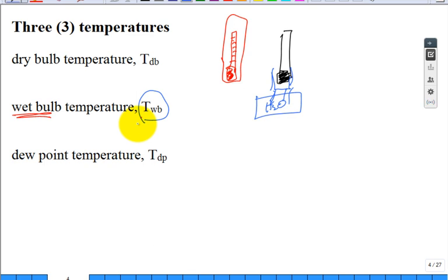So I can now turn it. I can put the two pieces together, push it in or out so far such that the 75 or 72 degree dry bulb mark matches with the 60 degree wet bulb mark, and I read off the relative humidity in this room. We're going to talk about relative humidity in a minute, but I'm going to pass this around.